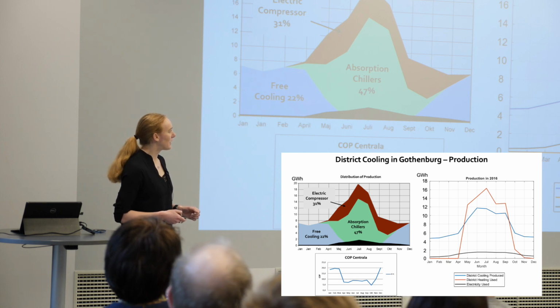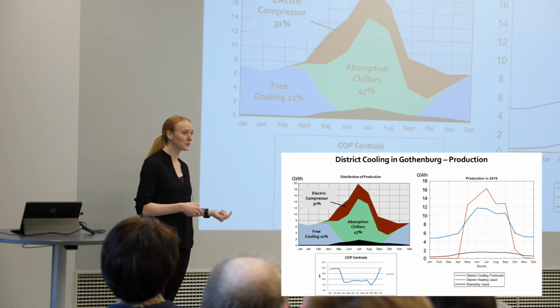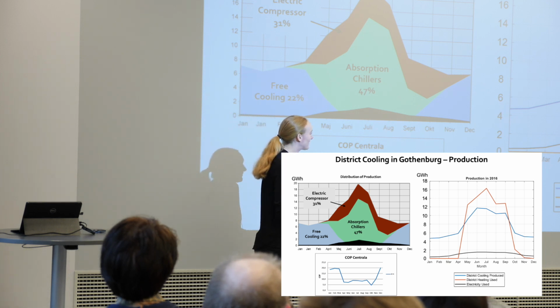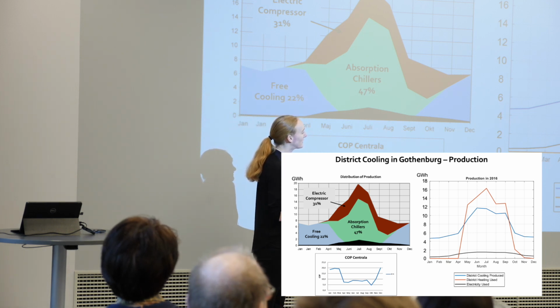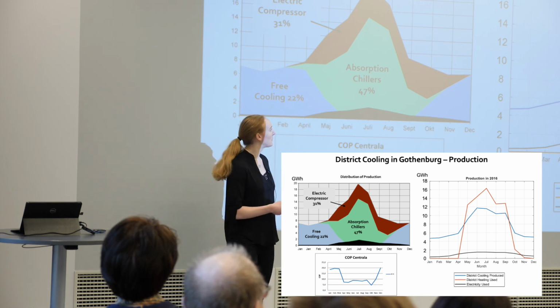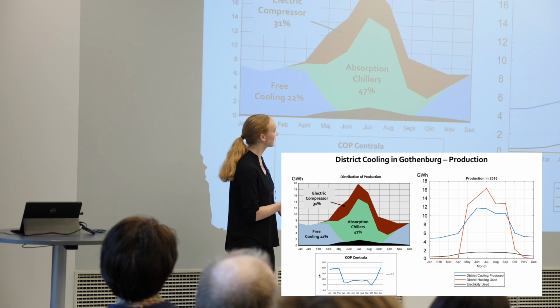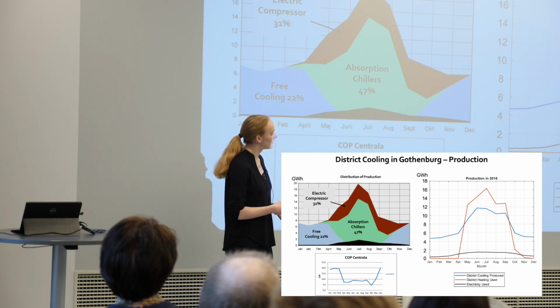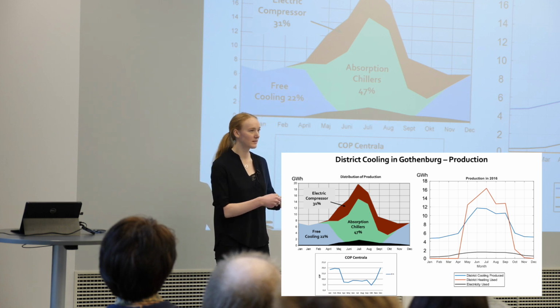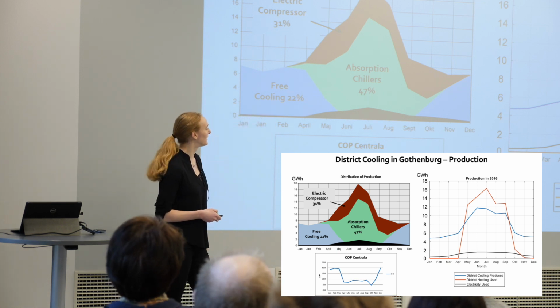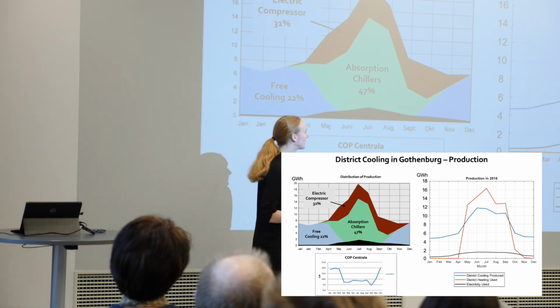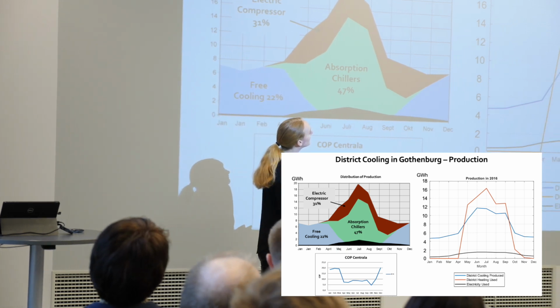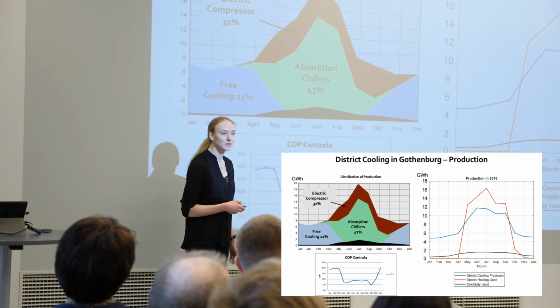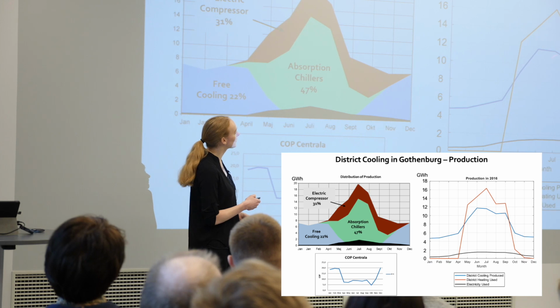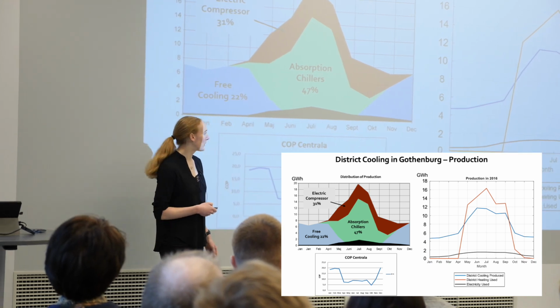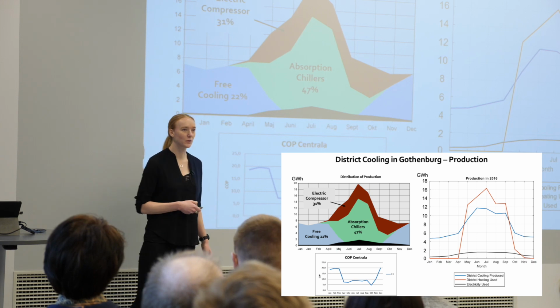And I also want to show you how much district heating is needed to produce the cold water. So the red line here, this is how much district heating is used per month in order to produce this amount of cooling, and also how much electricity is needed, so we get a sense of the scale of the energy needed here. So for example, in July, a little bit more than 16 gigawatt hours of district heating is needed to produce almost 12 gigawatt hours of district cooling, with 1.5 gigawatt hours of electricity for the month of July.